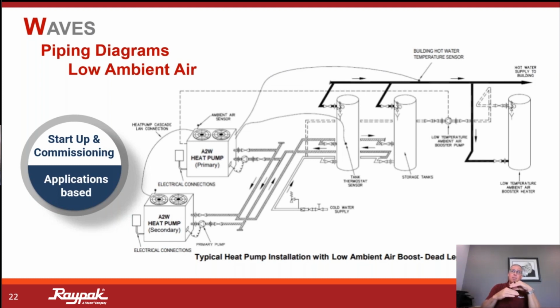And again, we're going to talk about this more thoroughly in the next segment on the air side rather than the water side. But at that point in time, we can do gas-fired backup. We can do this ambient boost temperature, typically an electric heater. So we'll talk more about other applications moving forward as well. But it will become more clear to you why we might need a booster heater when ambient air temperatures, let me state that again slowly and a little more clearly. When ambient air temperatures drop below a certain threshold, we're going to need some redundancy and some backup.